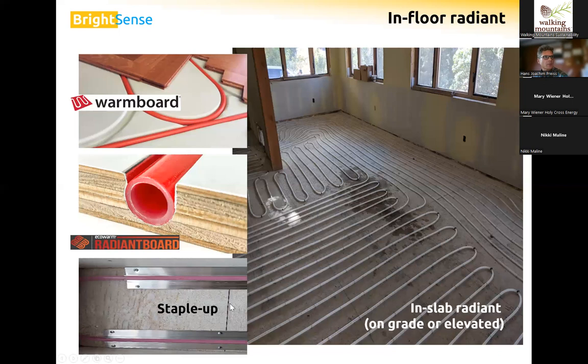Bottom left is a picture of staple up, looking at the floor joists up above with aluminum heat transfer plates. So the radiant piping snaps into those aluminum heat transfer plates, and the aluminum spreads out the heat a little further beyond the piping. So it's not a true staple up anymore.